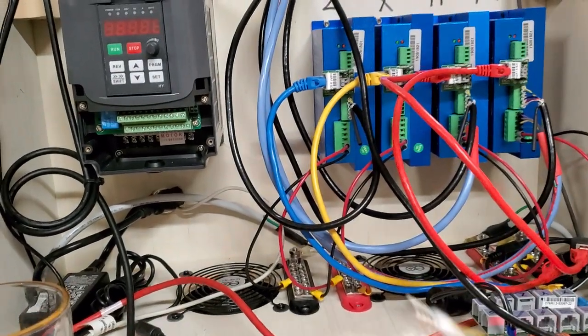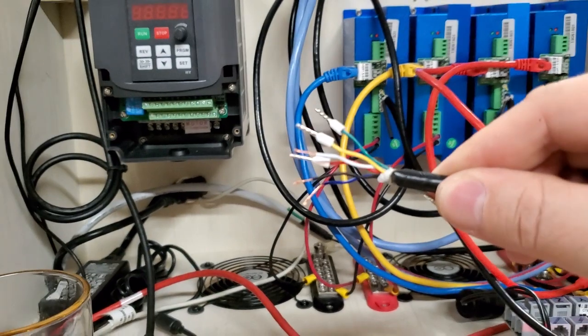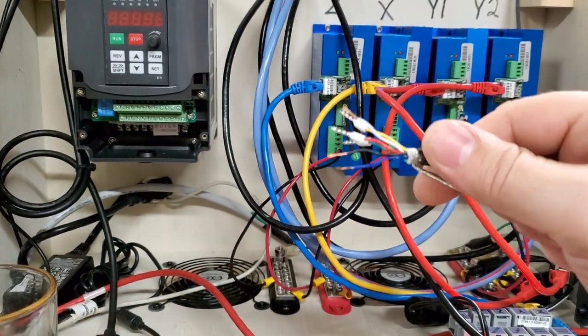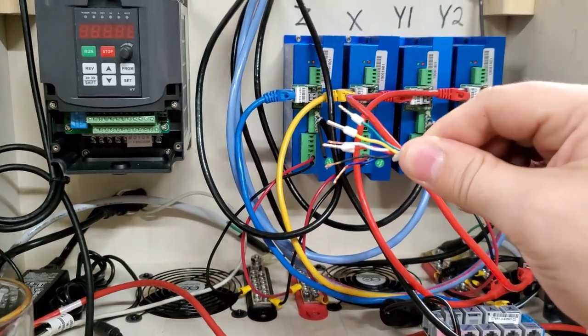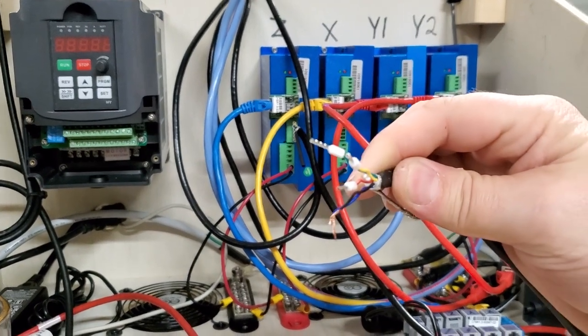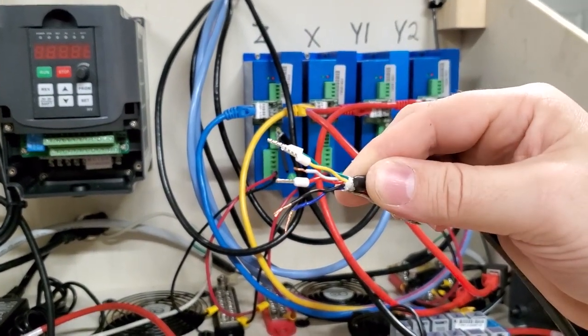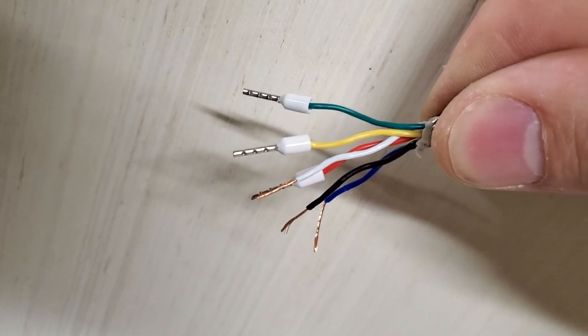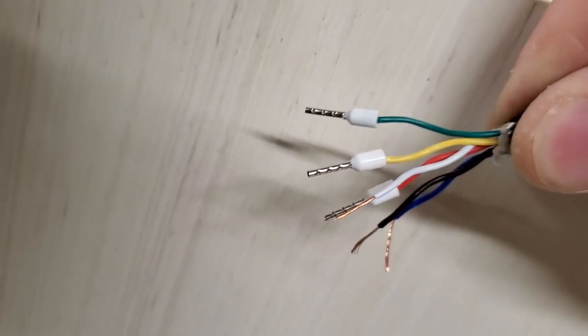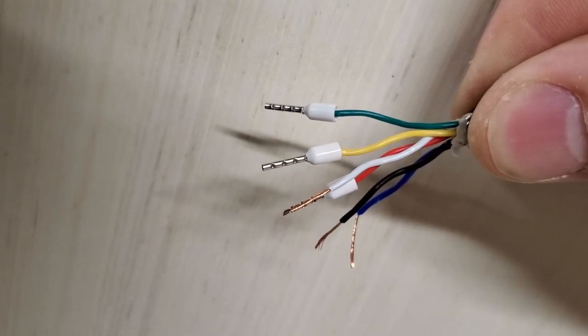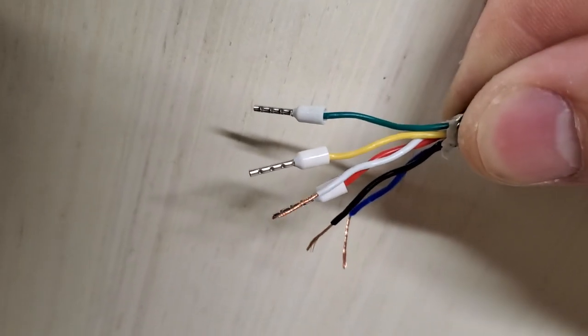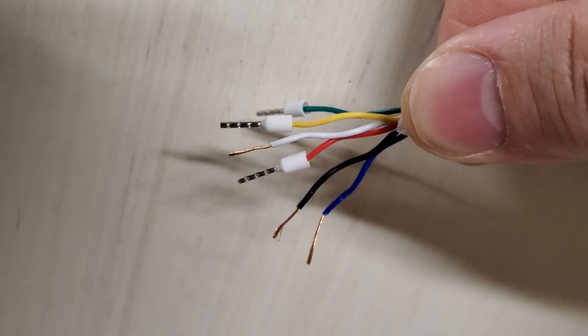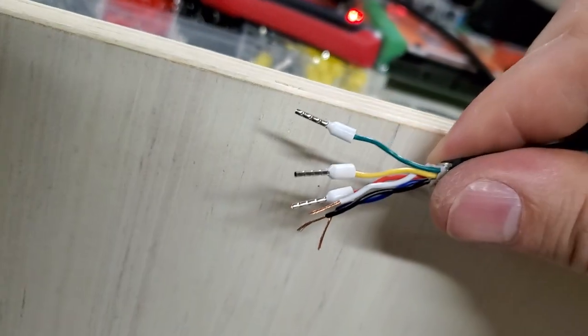But the ferrule, I hope you guys can see it right here, the ferrules are a really soft nickel plated copper. And I don't know if it's going to focus too well on them. But anyway, they're a really soft nickel plated copper, and when you screw down your terminal block it actually creates an indentation into the ferrule. And that little indentation will actually act as a set screw and it keeps the wire inside the terminal block.